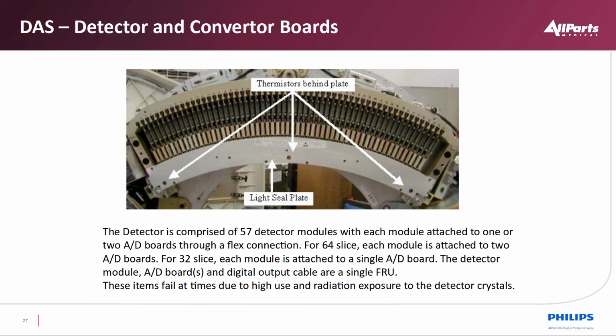On the detector side, the detector itself is not seen here. There's a plate covering it, but the elements are right behind that plate, feeding each of these converter boards. We are dealing with 57 detector modules in this case. These detector modules are FET-based, which means that they are highly sensitive to static electricity. Whenever a service engineer is in this area, not only are they dealing with normal static issues that they would expect in a computer or anywhere else, but the sensitivity is so much higher that they definitely have to be grounded when they're in this subassembly.